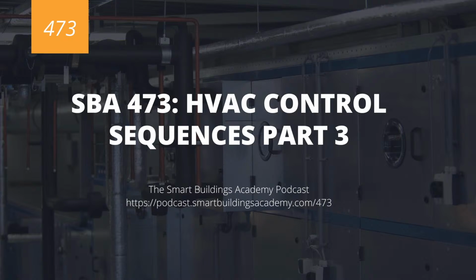So we've got those safeties, and then we have smoke safeties and fire alarm safeties, which are typically secondary monitoring. Those safeties will typically report back to the fire alarm panel, and we will typically have an auxiliary output off of that sensor or an auxiliary contact that we are running our wires through for our safety circuit. By the way, that's what these things are called. We call it a safety circuit, and you often see it on controls diagrams where the actual design submittal will have all of these different coils and or contacts that are going to be energized by safeties, and you're going to see your control signal passing through that.